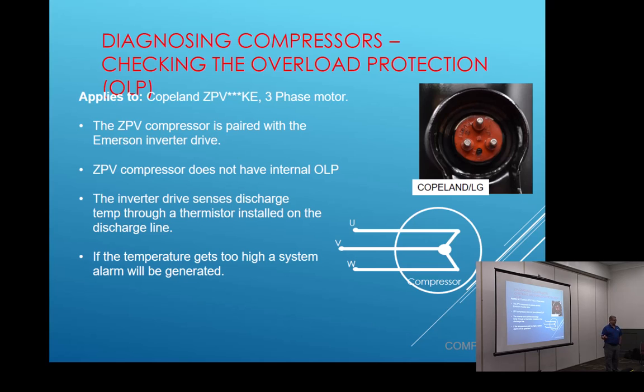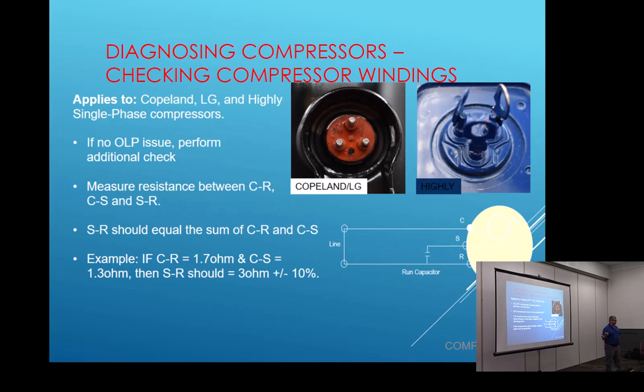Okay. So that being said, our Copeland scroll compressors and our LG and our highly rotary, it's a single phase compressor. So we check it just the normal way, right? Common, start and run and everything, 1.7, 1.3 should end. Our start and run should end up to the sum of those other two, right? So it's not a 3-phase, it's a single phase compressor. So don't get them mixed up and thinking, well, that highly rotary, it's a 3-phase. Boy, my things are all wrong. I got a bad compressor. No, it's just a single phase compressor. And we're going to show you how that works later on with that inverter drive.